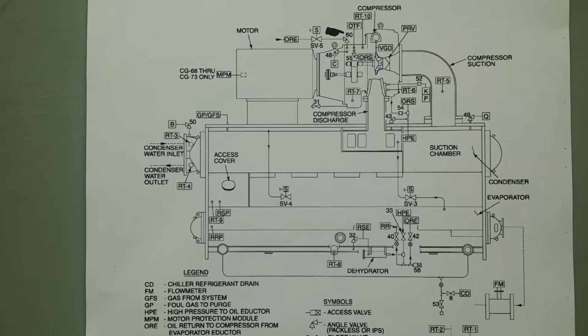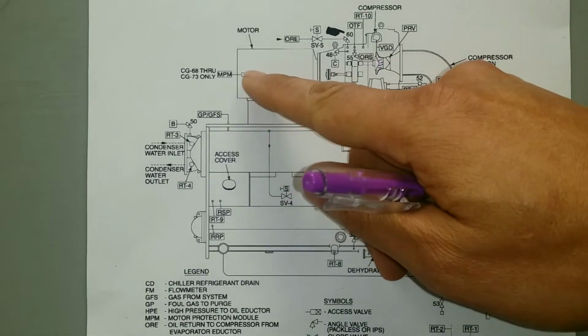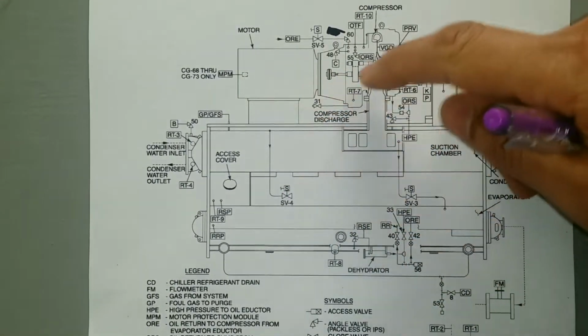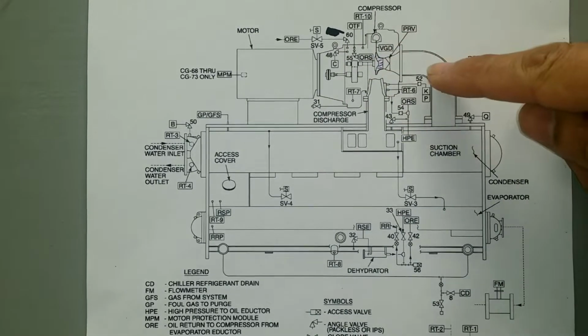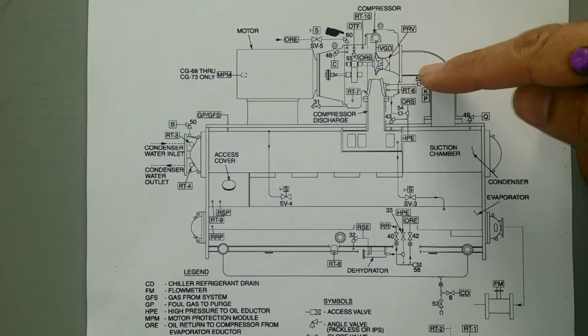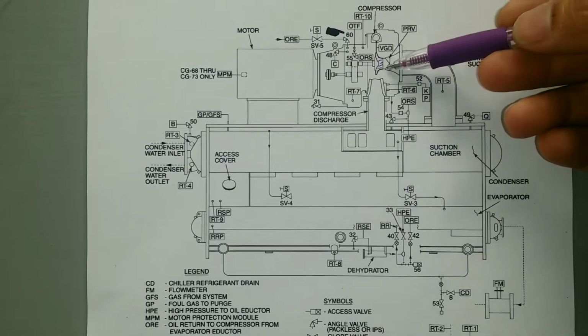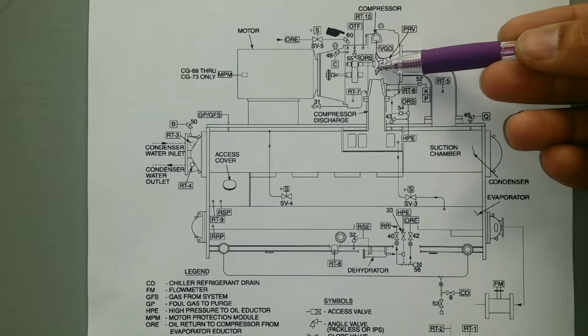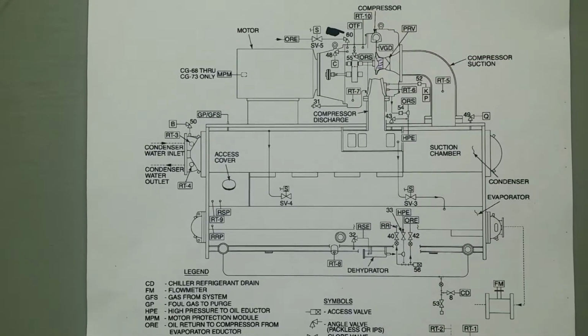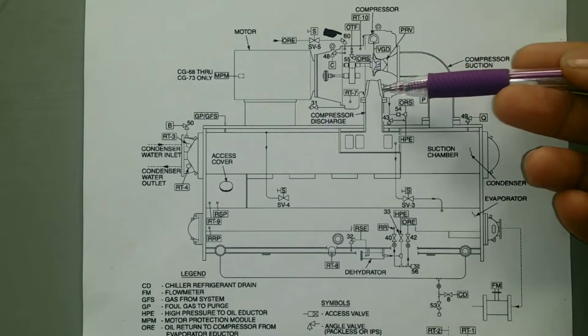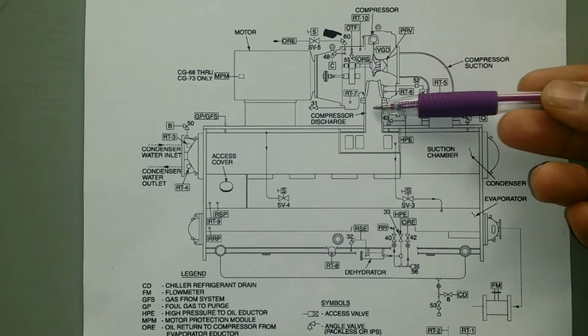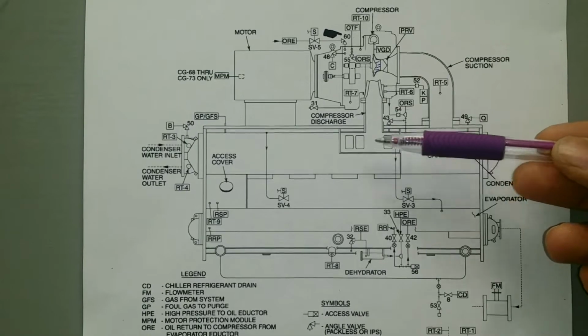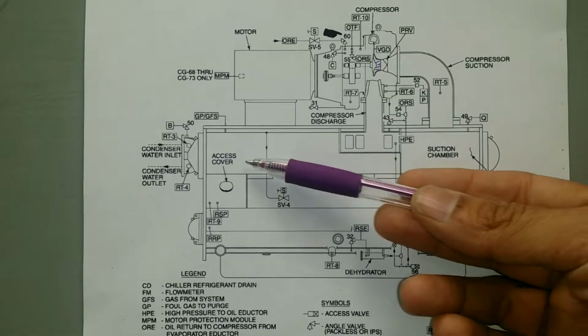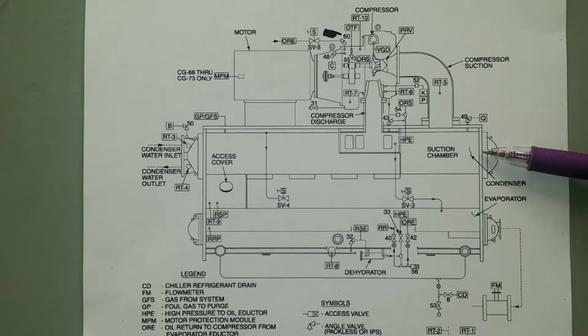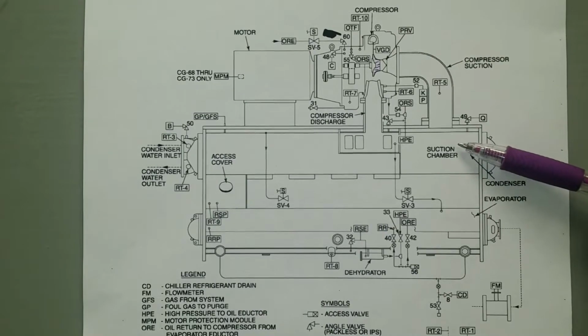So, as I've done in other videos, first I start with theory of operation. As you can already tell, there's a motor over here, and then there's a centrifugal compressor over here. And on this side, we've got a low pressure refrigerant gas. As the impeller starts to turn, it will exhaust the refrigerant into this chamber over here, which is called the condenser. From this point on, the refrigerant is at a high pressure, but it's still a gas.